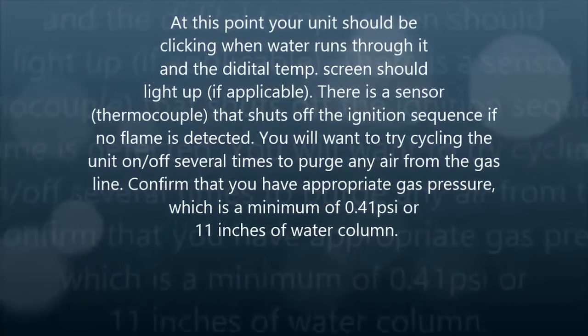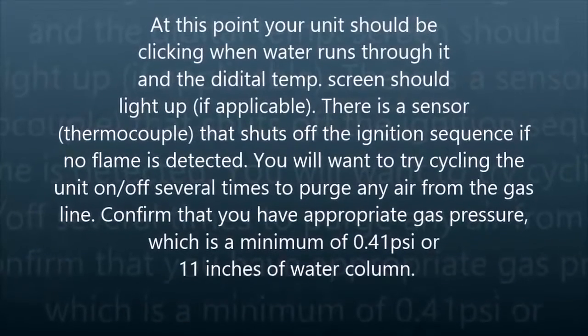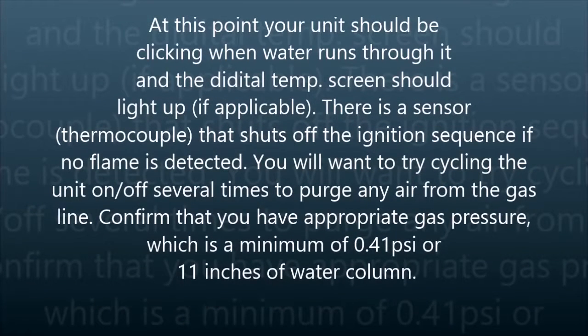At this point, your unit should be clicking when water runs through it, and the digital temperature screen should light up if applicable. There is a sensor that will shut off the ignition sequence if no flame is detected. Try cycling the unit on a couple times to purge any air in the gas line out.